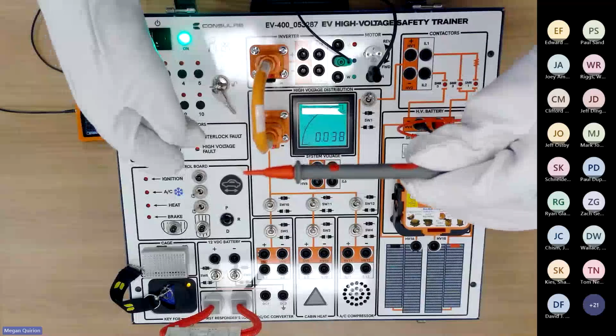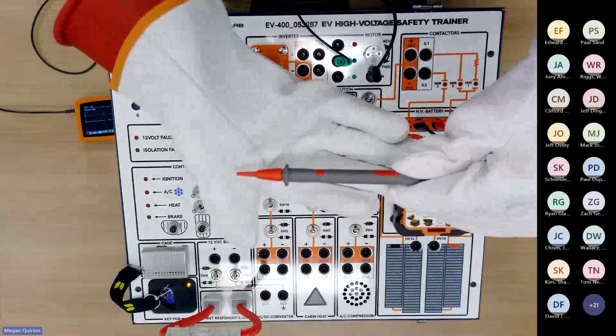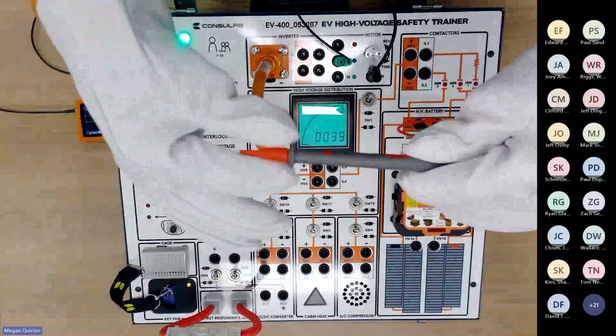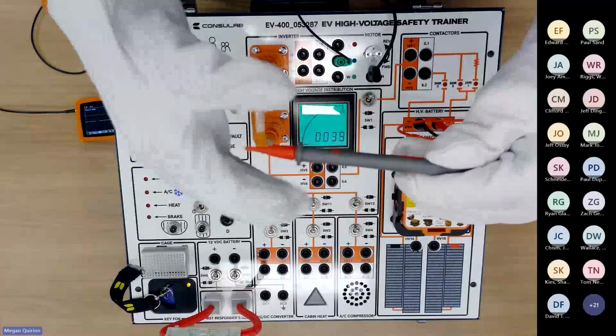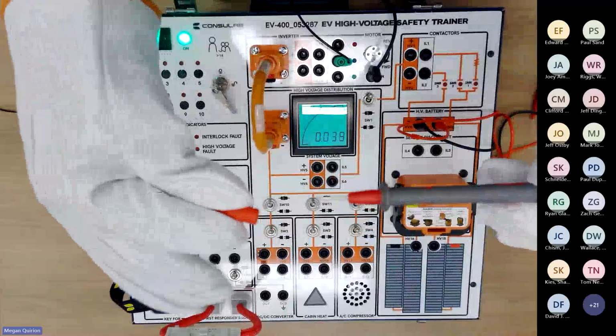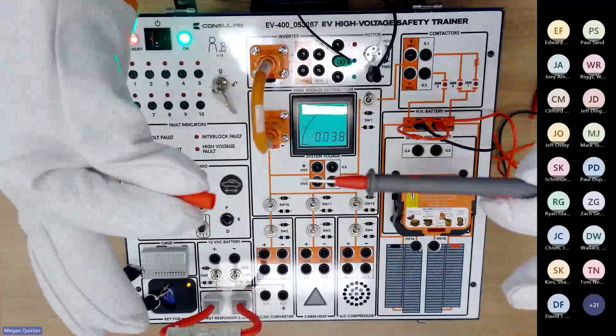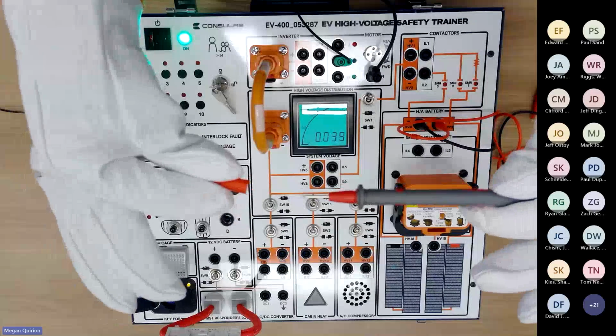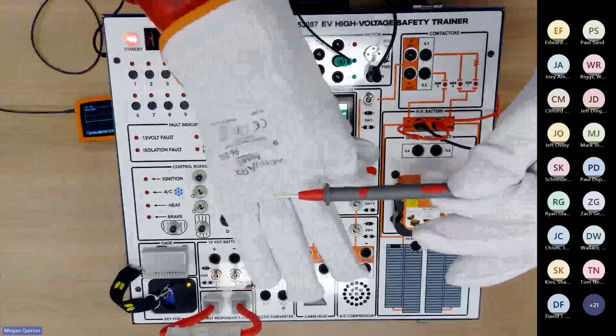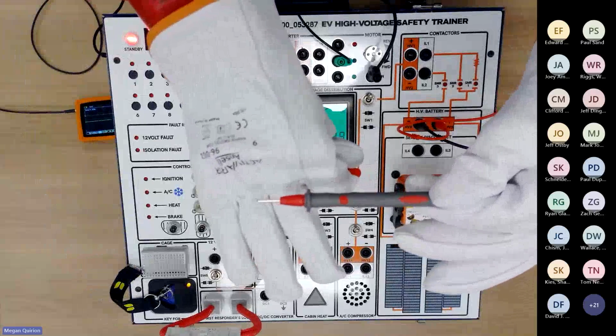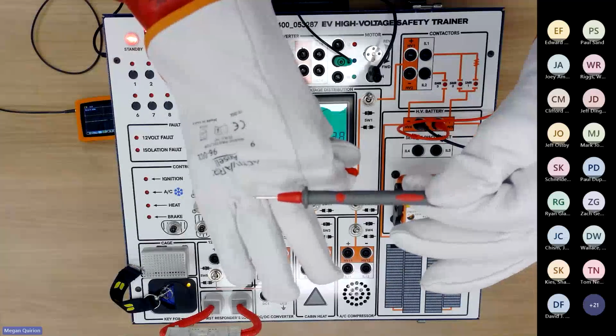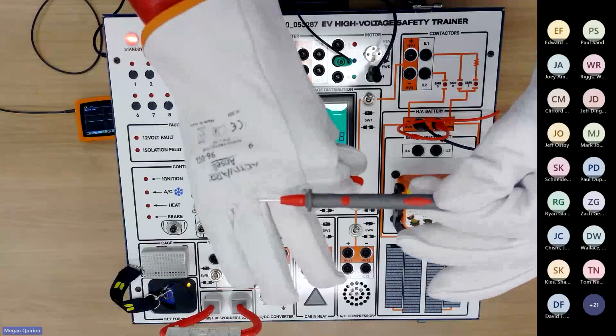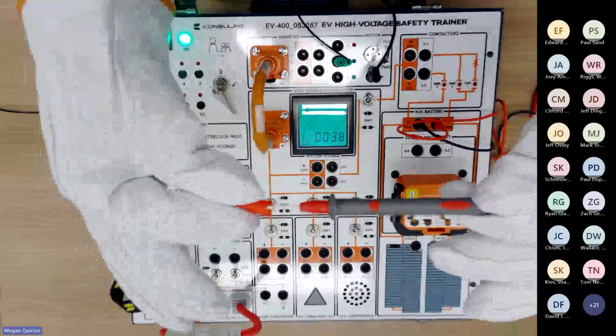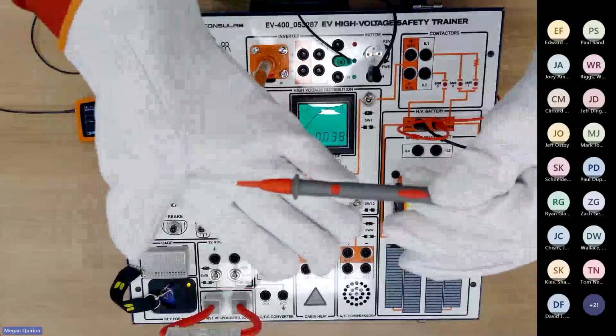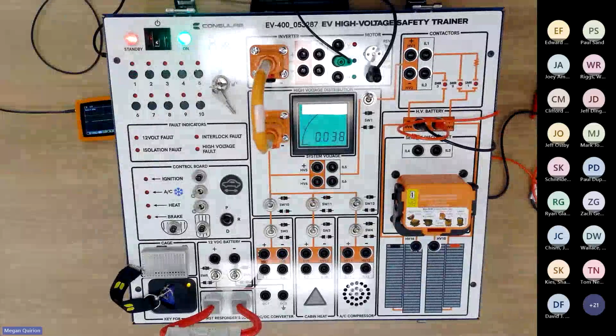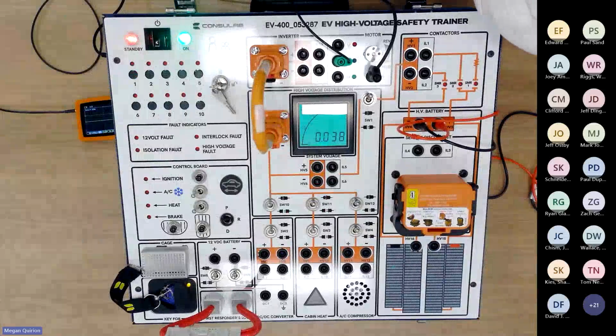Even with that number on the lead, you want to make sure you have the proper protective cover on the end of it. You can see how this one pulls off. If you pull that cover off, you've exposed about an inch of probe that could potentially touch and cause a shock, so it's no longer a Cat rated lead for the same capability of Cat 3 or Cat 4. So to test high voltage, you have to make sure that cap is on the end.